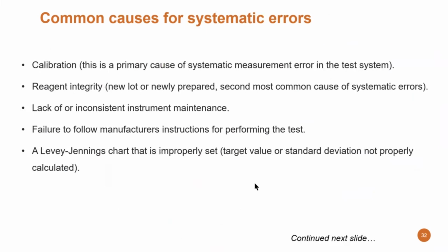Common causes for systematic errors: that's the calibration. This is a primary cause of systematic measurement errors in the test system. So please take most of your action to have a proper calibration and use the right calibration material, following again the instruction of the manufacturer of the reagent. Reagent integrity: a new lot or newly prepared reagent may behave differently. Check always the lot number, even if you have used it for a while, check if it has changed. The second most common cause of systematic errors is the reagent lot to lot situation.